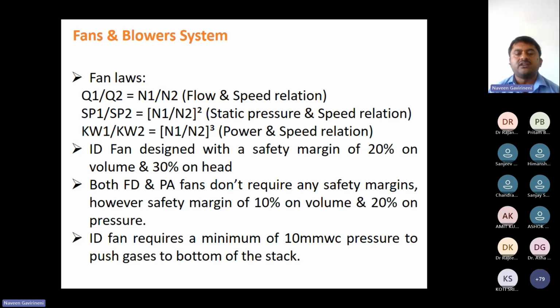Why? Because they are given as per the design, but in case of any incident we need a margin on the fans. So the ID fan is meant for a 20% margin on volume and 30% on head, while the FD and PA fans have less margin. Why? Because the ID fan is more critical than those. If you do not extract the flue gas, what happens? The boiler is going to collapse and there is a huge loss of men and machinery. So both FD and PA fan arrangements have safety margins. The ID fan requires a minimum of 10mmWC pressure to push the gases. The ID fan extracts the flue gas from the furnace and sends those gases to the stack. After the stack, it goes to the atmosphere.